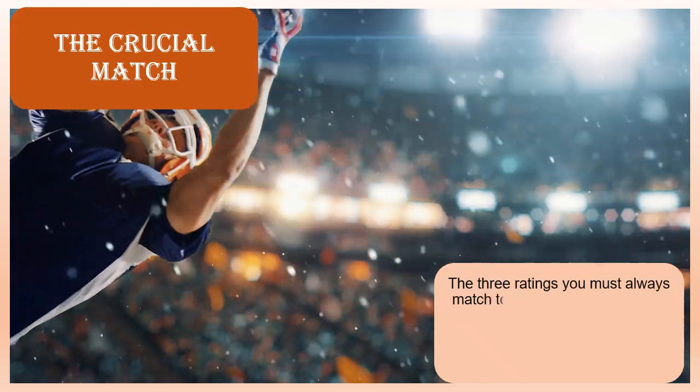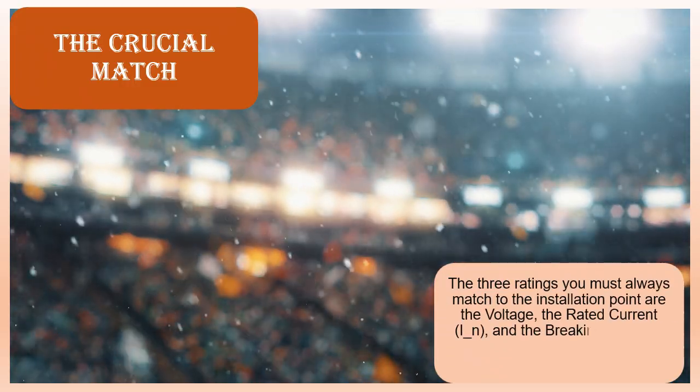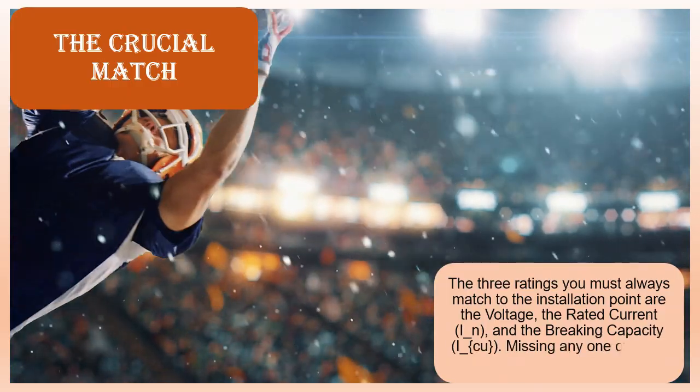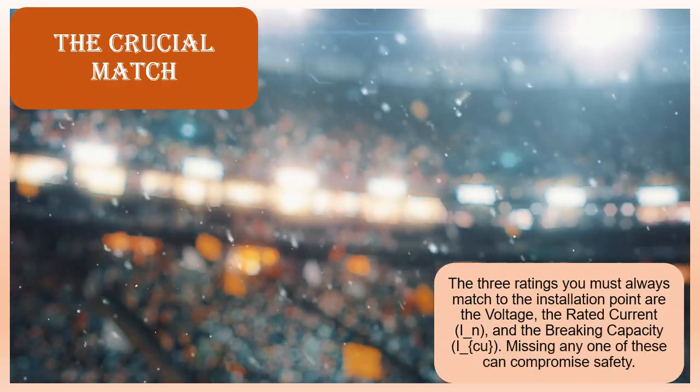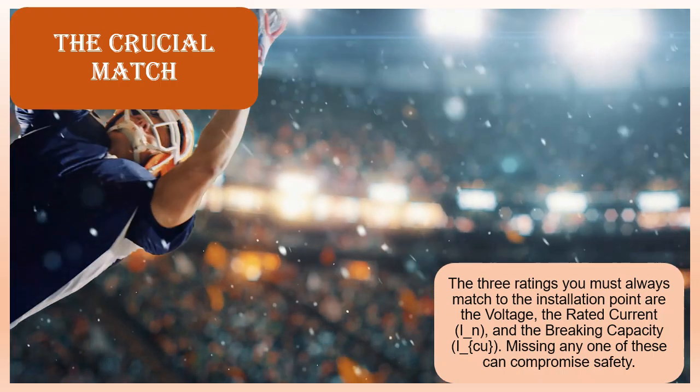The crucial match. The 3 ratings you must always match to the installation point are the voltage, the rated current, I_N, and the breaking capacity, I_cu. Missing any one of these can compromise safety.